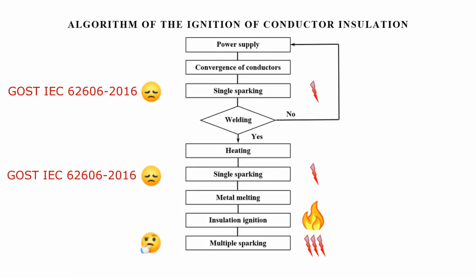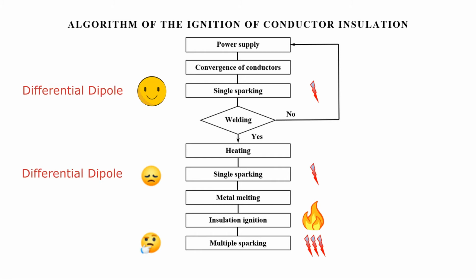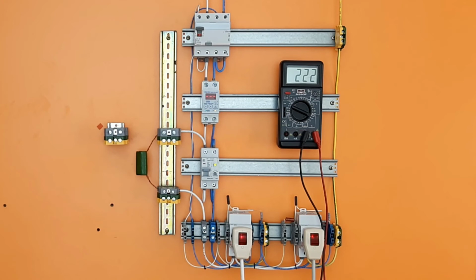Here it is appropriate to open a slide from another of our films and see what problem we have solved. Let me remind you that the problem with the AFDDs according to state standard 62606 was that they could not turn off the power at the initial stage of the accident. They hit the tail, so to speak, when the shutdown became useless. In comparison with the arc generator with carbon electrodes, we actually see single sparks and sticking of the electrodes on copper and aluminum. To detect such damages, the sensitivity of differential current devices is just required. They are at our connection structure, can timely prevent the dangerous development of events, as there is a control of the first single sparking.